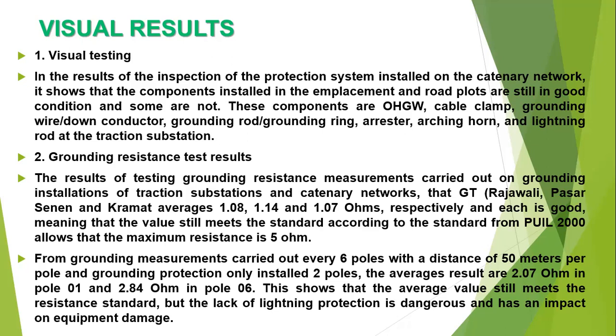From grounding measurements carried out on 6 poles with a distance of 50 meters per pole, and grounding protection only installed on 2 poles, the average results are 2.07 ohm in pole 01 and 2.84 ohm in pole 06. This shows that the average value still meets the resistance standard, but the lack of lightning protection is dangerous and has an impact on equipment damage.